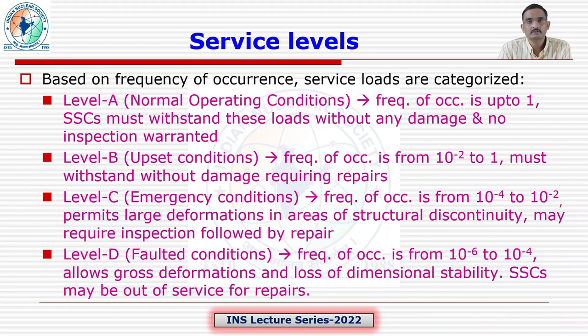The last level is level D, or faulted condition. Here, frequency of occurrence of these loads is from 10⁻⁶ to 10⁻⁴, meaning these loads are expected less than once in 10,000 years. So here, the design allows gross deformations and loss of dimensional stability, however structural integrity of the system has to be maintained. The structure, system and component may be out of service for repair after experiencing these loads. The service loads, their combinations, and their applicability to various service levels are identified and are part of the design specification.